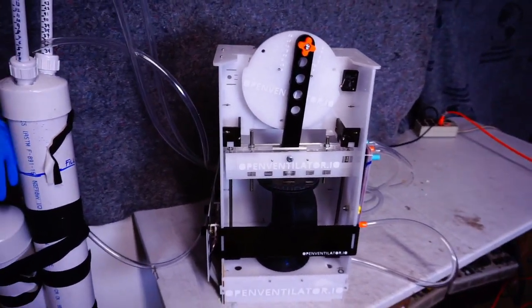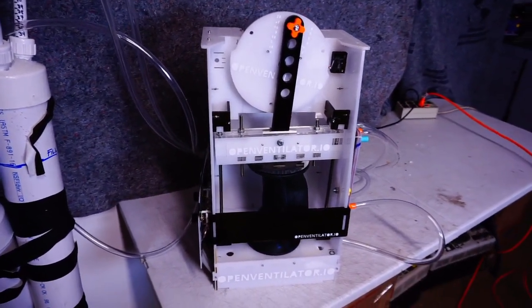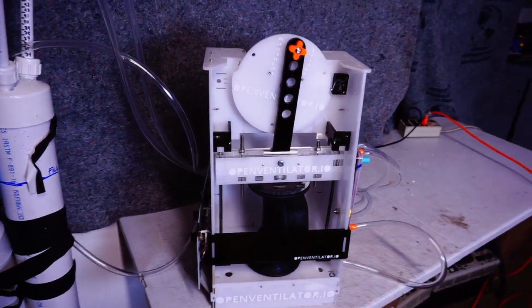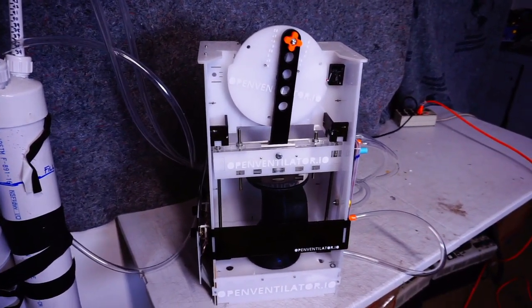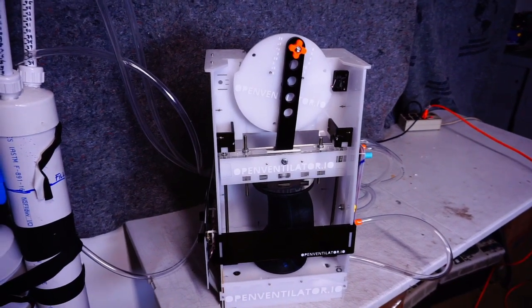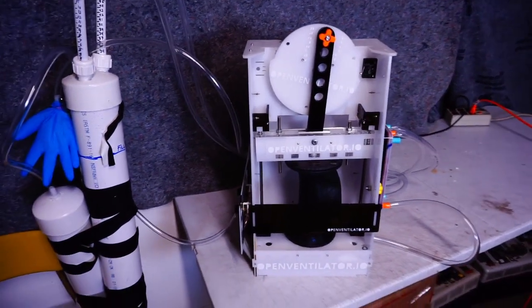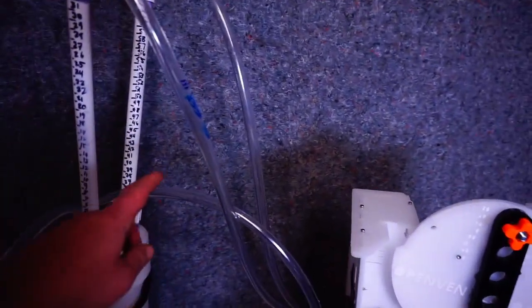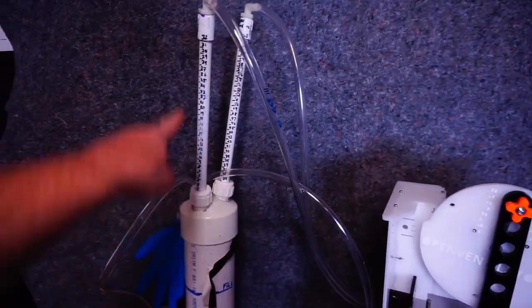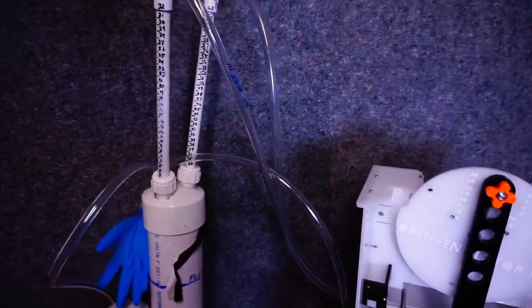One of the things we would like to see is an empirical calculation and a chart possibly of pressures in the system and induced patient volumes at peak. One other thing we would like to add is, I'm out of T's, but along the overpressure line we could easily add a T and a U-tube manometer, something like this, so you could read peak pressure in the system, which should be maintained by a check valve on this overpressure line. Let me turn the machine back on.